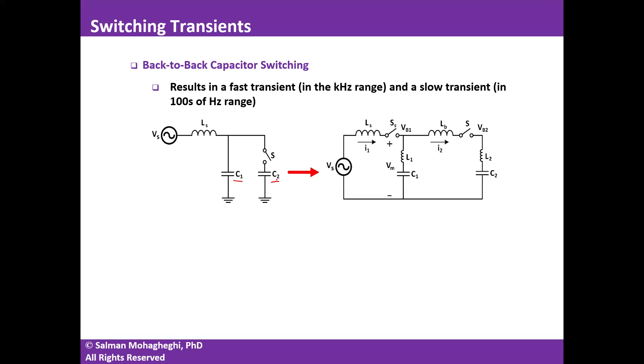Usually we switch capacitor banks on or off when the system current is at zero. This reduces a lot of current transients, but because the system is very inductive or very capacitive, when we're at the zero crossing of the current, the voltage is going to be very close to peak value — either positive peak or negative peak.